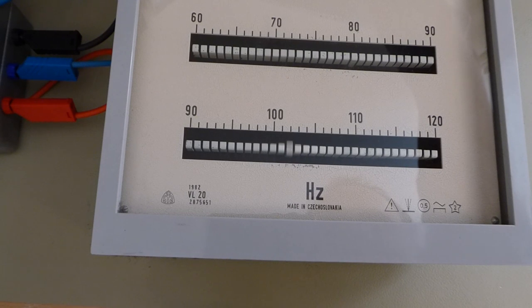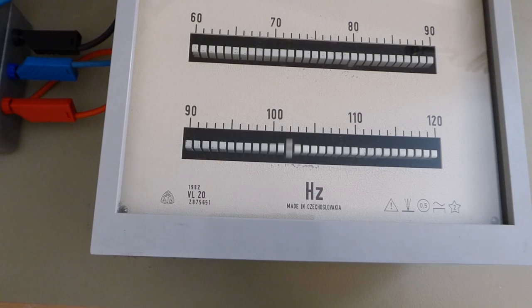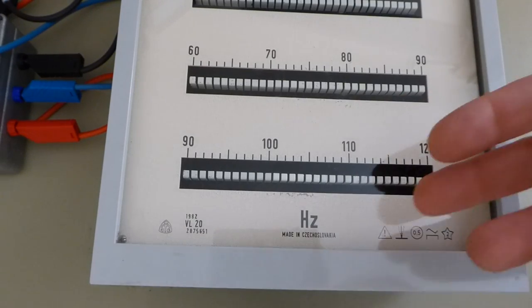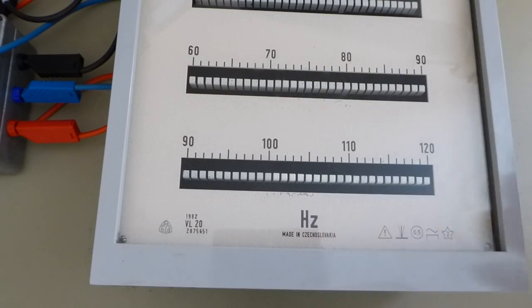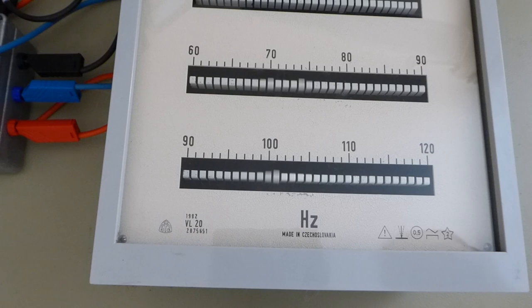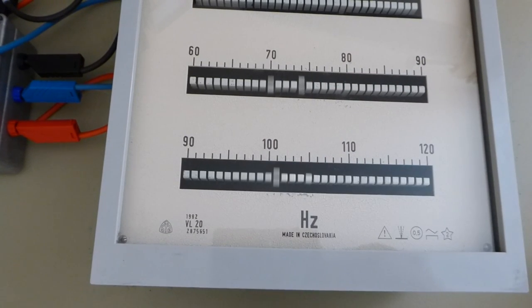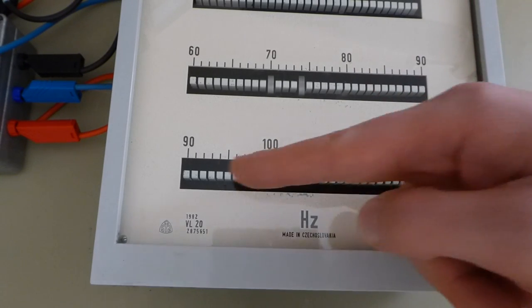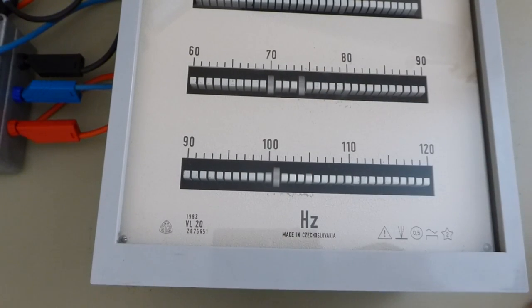Now, there are a few really cool things you can do with these. One of the main things to realize is that, as I said before, each of these reeds has its individual resonant frequency. So it doesn't just read out one frequency, but it can read out multiple frequencies at the same time if you excite multiple reeds at the same time. So just to show you a demonstration, I prepared a signal that has three different sine wave components to it. And you can see we have the 70, the 74, and the 101 Hz reeds vibrating simultaneously.